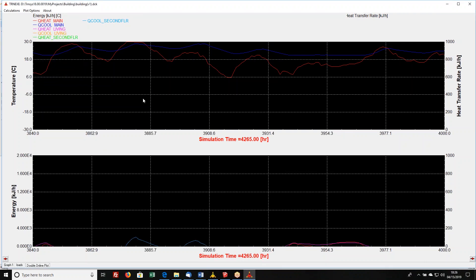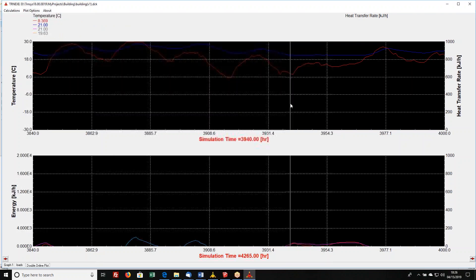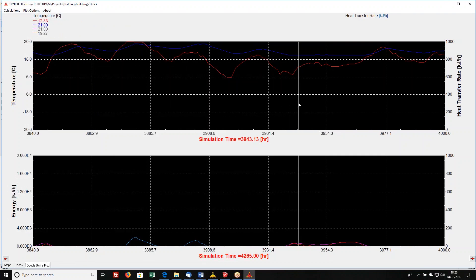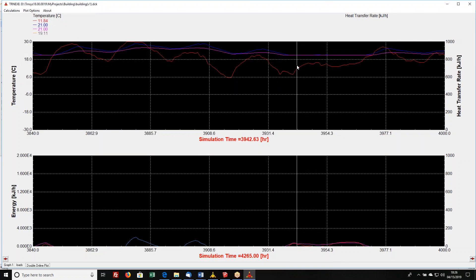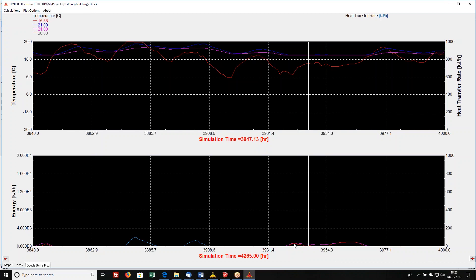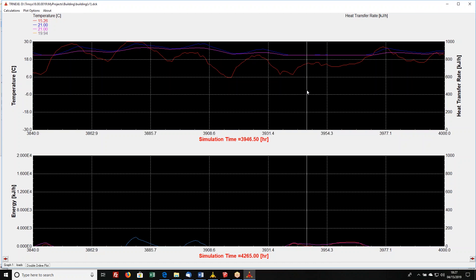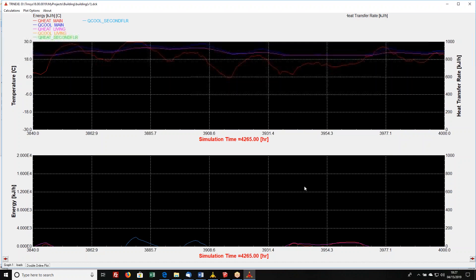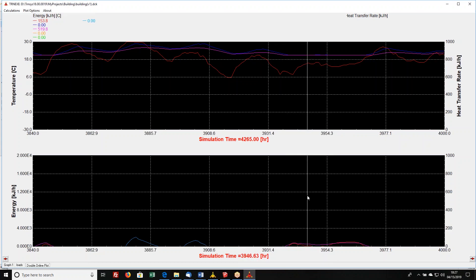So when we see up here that blue line not coming down below 21, and in fact both the living and the main zones are bottoming out at 21, then if you look down on the plot below, we're seeing that there's some heating load there. Unfortunately, there's not a way of seeing the values on both plots, so whichever plot you click on, so here I'm clicking on the top plot, and the labels up at the top of the screen show what's going on in the top plot. If I want to see what's going on in the bottom plot, I just have to make that the active plot by clicking on it, and then you see that the labels up here have changed, and here you can see that in fact there's heating load going on.